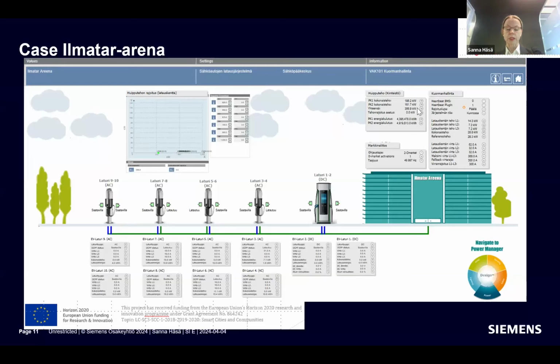So for example, if someone is charging their car at this 160 kilowatt charging point, and they would charge really at 160 kilowatt, then in case needed we can limit the power so they will get only 150 kilowatt or 130 kilowatt. Of course we don't cut all the power off, because that would be very bad service to the person charging there. But we will cut the power based on need at these charging points, so they still get power, but it's okay for the limits of the grid, also taking into consideration the PV power production and the total consumption.